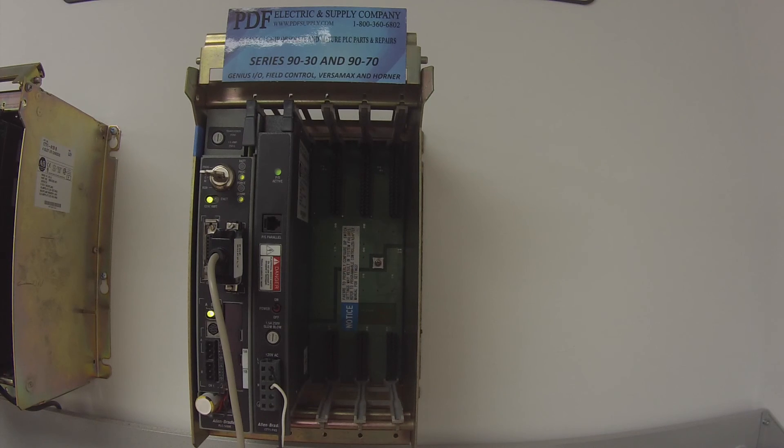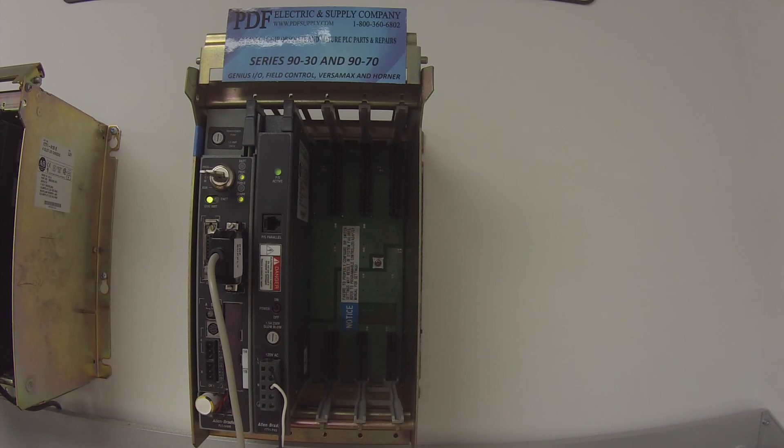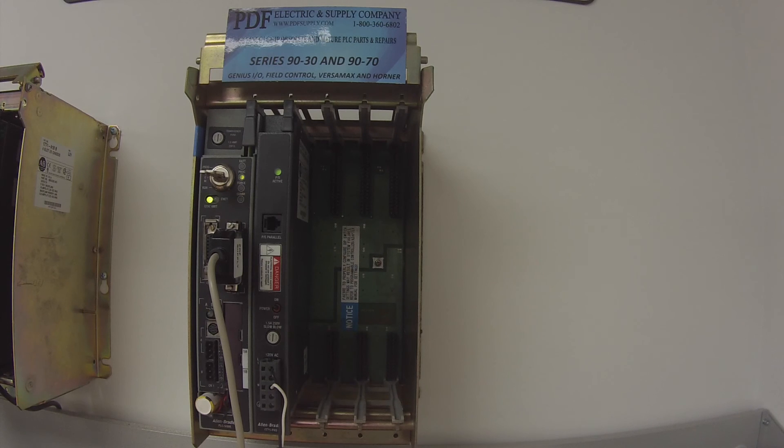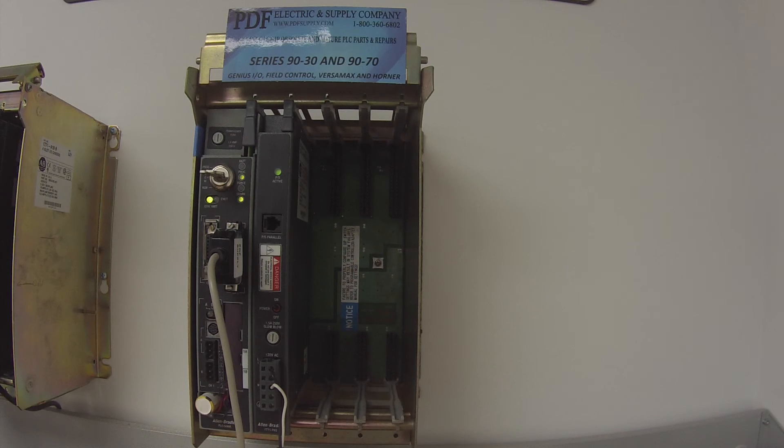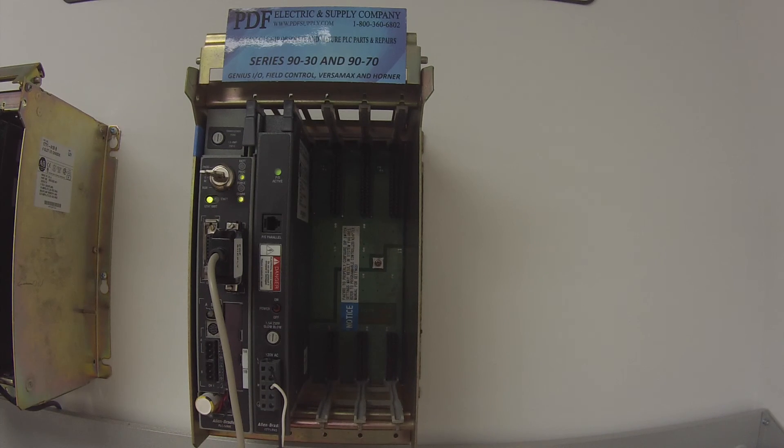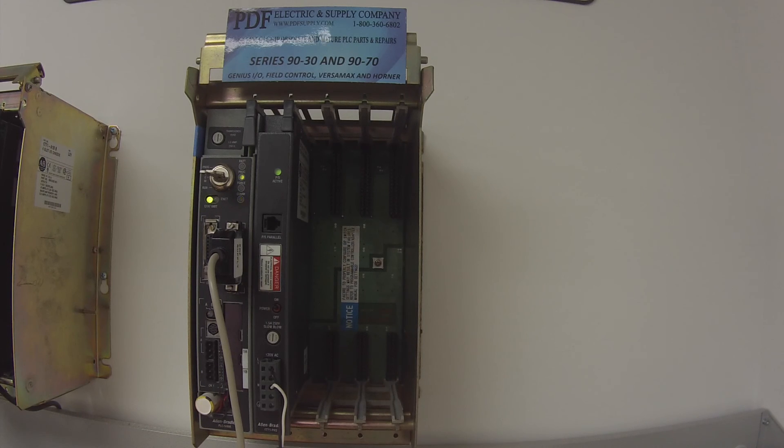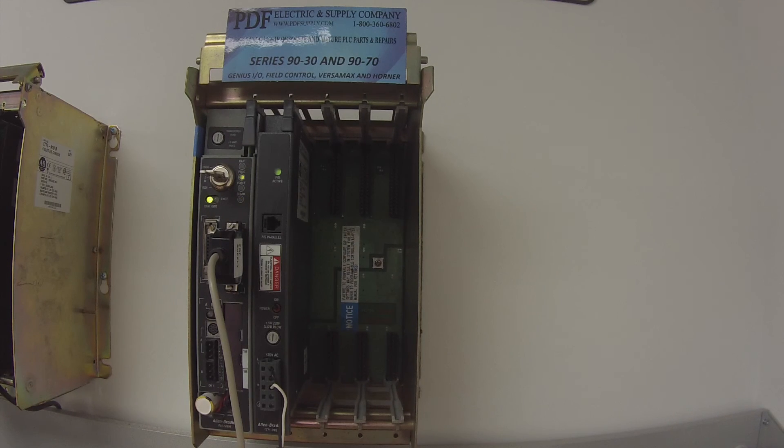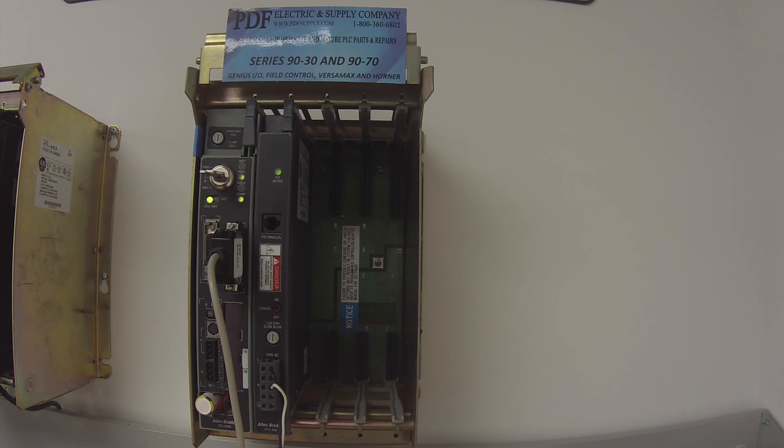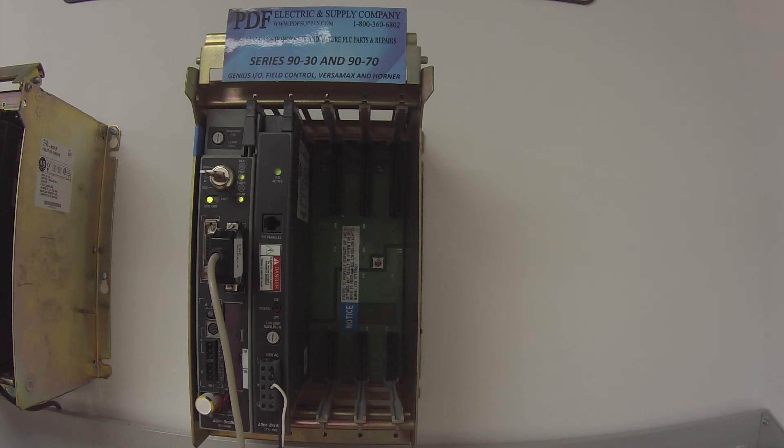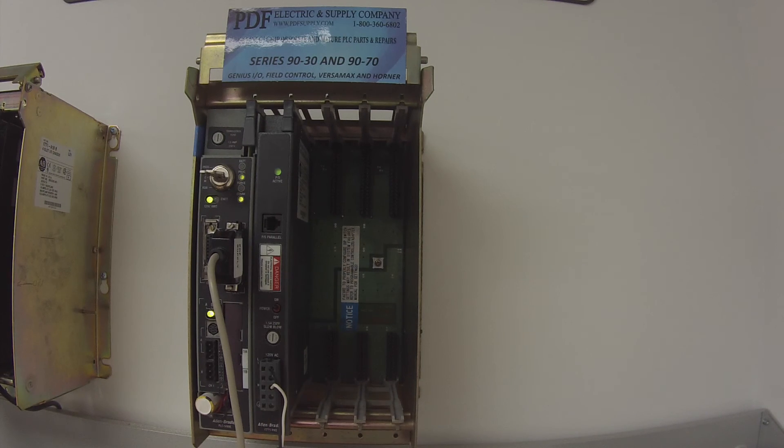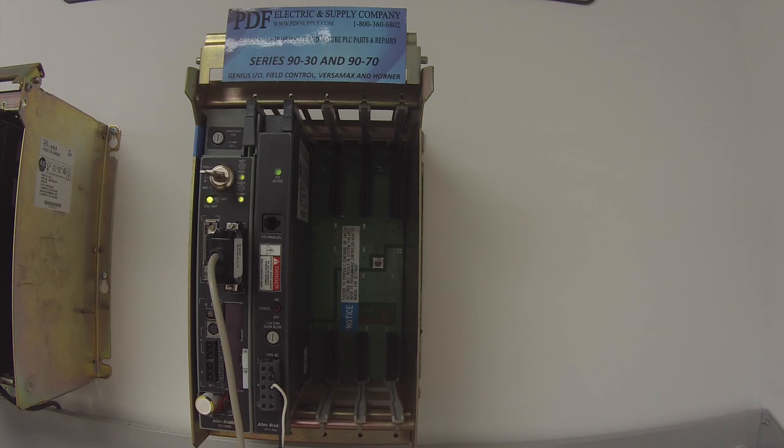What I normally do is I'll keep the processor running for a couple days, two or three days, maybe over a weekend, and come in and check on it and check the diagnostics as I showed you before, the processor status. I'll check to see if it's still in run mode. If it's kicked itself out of run mode, I might want to go into the errors and find out why, see what the problem is.